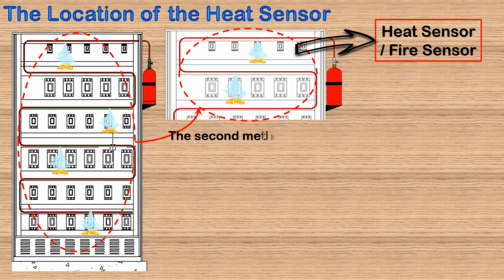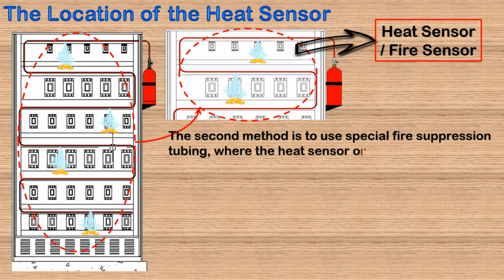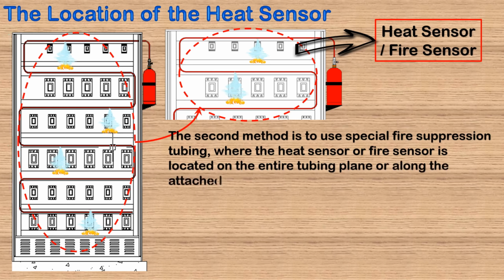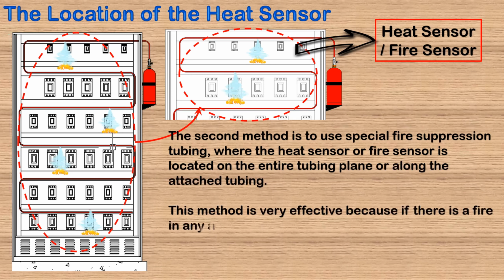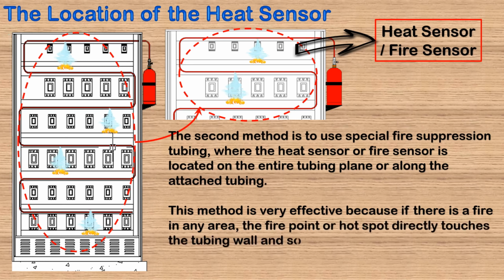The second method is to use special fire suppression tubing, where the heat sensor or fire sensor is located on the entire tubing plane or along the attached tubing. This method is very effective because if there is a fire in any area, the fire point or hotspot directly touches the tubing wall and breaks it so that it can spray liquid media to extinguish the fire in the fire point area.